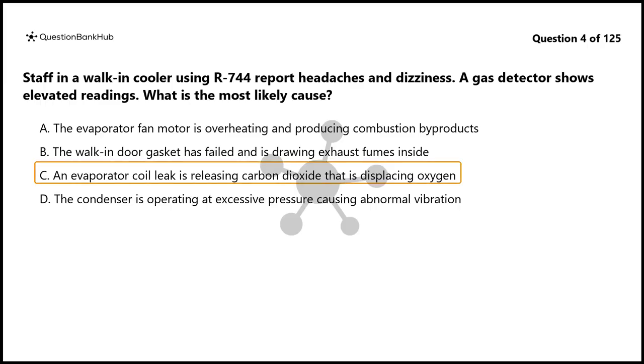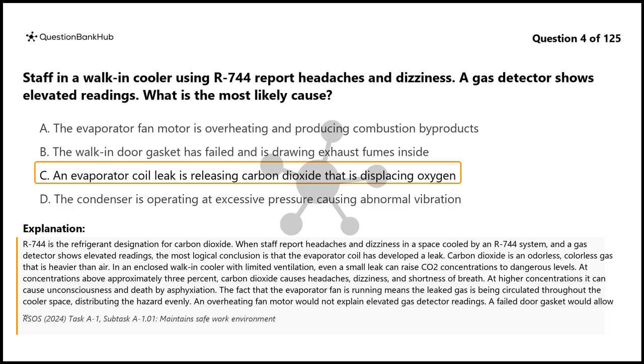The correct answer is C. R744 is the refrigerant designation for carbon dioxide. When staff report headaches and dizziness in a space cooled by an R744 system, and a gas detector shows elevated readings, the most logical conclusion is that the evaporator coil has developed a leak. Carbon dioxide is an odorless, colorless gas that is heavier than air. In an enclosed walk-in cooler with limited ventilation, even a small leak can raise carbon dioxide concentrations to dangerous levels. At concentrations above approximately 3%, carbon dioxide causes headaches, dizziness, and shortness of breath. At higher concentrations it can cause unconsciousness and death by asphyxiation.